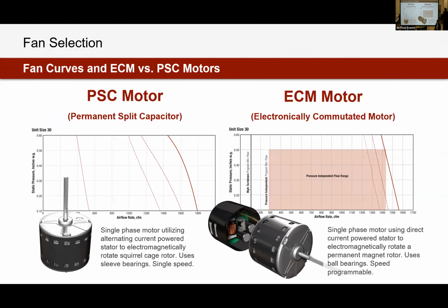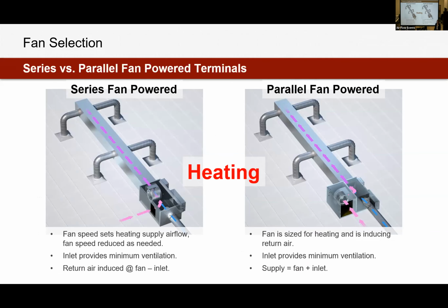Fantastic. What do you see more of now? It used to be that series was more frequently used, but now it seems like parallel is considered more energy efficient. Other way around, yeah. Parallel was very common for the longest. They were pretty even with each other, and now series is kind of taking off because of its energy efficiency. Previously with PSC motors, your old style, not really adjustable motors, the parallel box is more efficient because your fan was not always running. You only ran the fan and used that energy when you needed it to, whereas in the series box, you always had to run an inefficient motor. Nowadays, with ECMs, or EC motors, the series box is more efficient, even though your fan is always running.